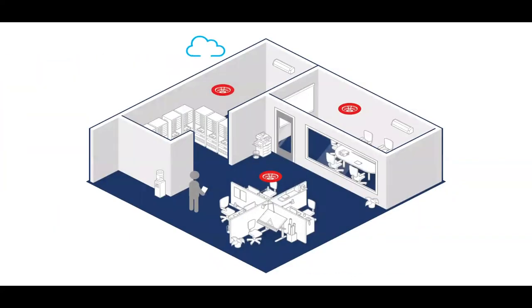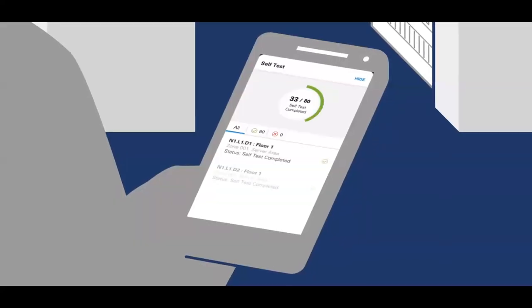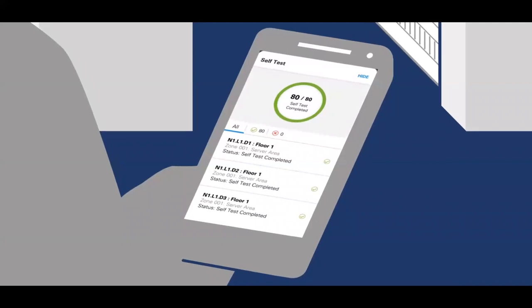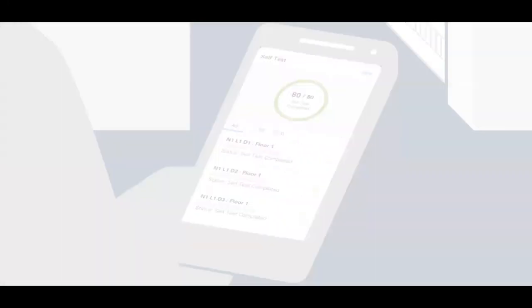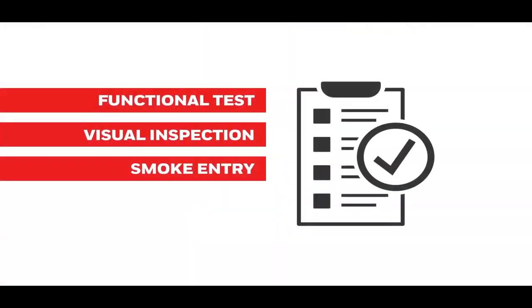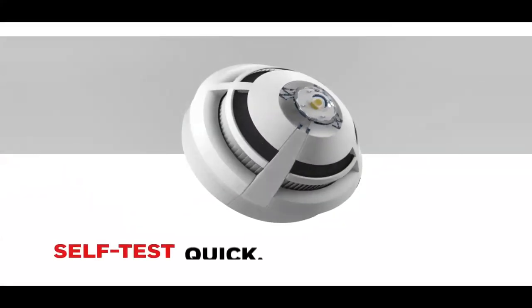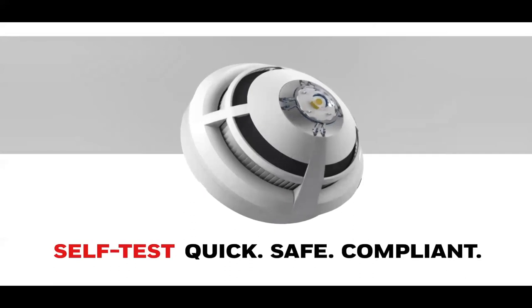So if that detector goes off into fire out of the sequence that they're meant to be tested, it will kick him out of his test and it will go into an automatic evacuation. So it's a smart system. It recognizes what it's meant to be doing. So during the time that it's in test, you don't isolate your fire alarm from working. It's still doing what it's meant to do. So that's where the self-test is going.